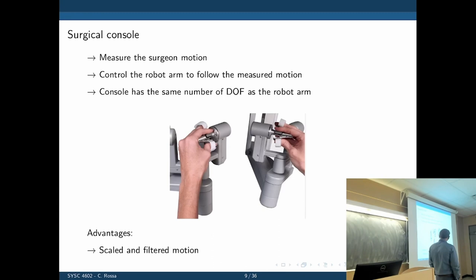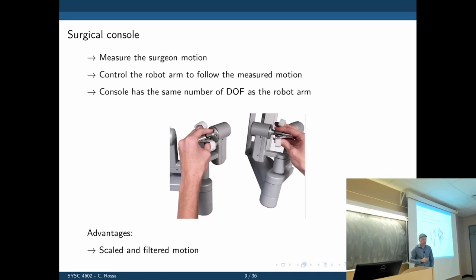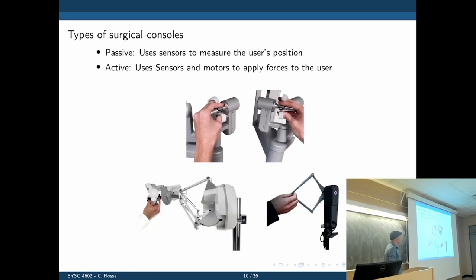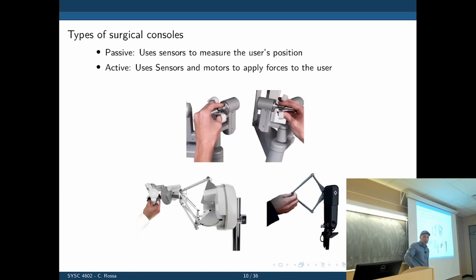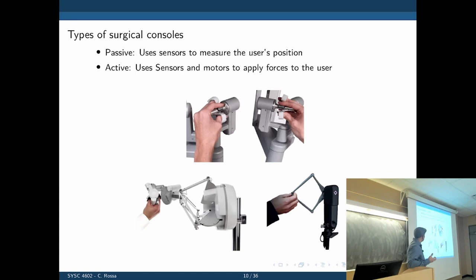Here is a closer view of the joysticks. This one is a seven-degree-of-freedom system that allows three rotations, three translations, and also grasping an object — the seventh degree of freedom to control forceps or similar tools simulated in a remote environment. We have two types of joysticks: passive and active. The distinction corresponds to their ability — or not — to produce force. In a passive joystick, all we can do is measure the user's motion. There is no way to apply force back to the user — it is basically a fancy position sensor that measures position and orientation of your hand and gripper.